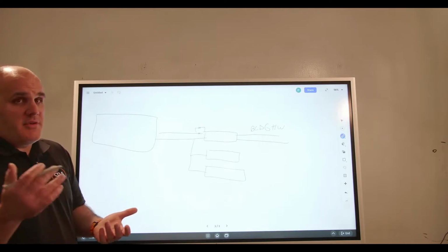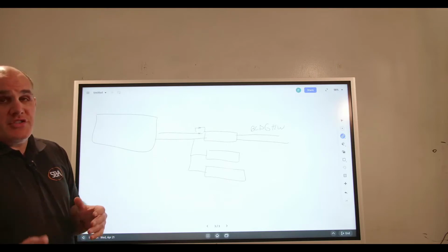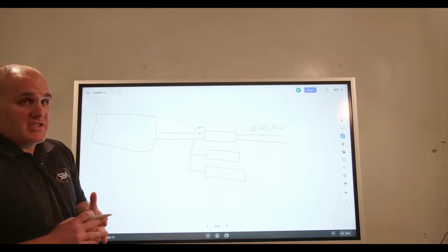We get into steam in our larger buildings, especially buildings that have 100% outdoor air dampers, like hospitals, where we really need to impact that preheat for that 100% outdoor air as fast as possible. We use that 1/3, 2/3 concept to drive and control the heat from the steam. And then in the case of building distribution, we're going to be using tubular heat exchangers. So that being said, I'm going to step over and see if we got any questions, and we'll go from there.